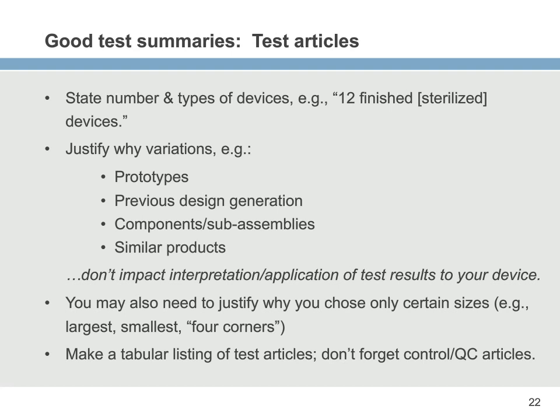You may pull a test from 10 years ago on a similar product and say, look, that's all we need to do. We don't need to redo this testing. So it could be an awful long list of variations about why you have to test it. And you also need to make it clear why they don't impact the interpretation or application of the test results. So, we tested a component because the rest of the device outside that component simply doesn't affect how that particular component works in that way.